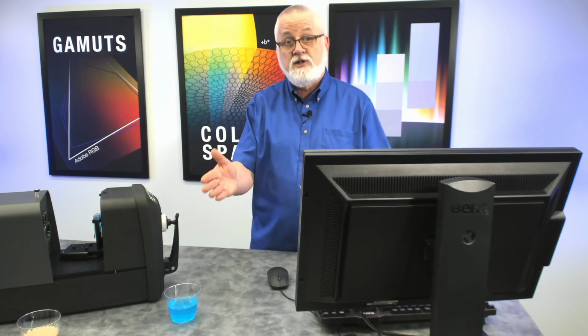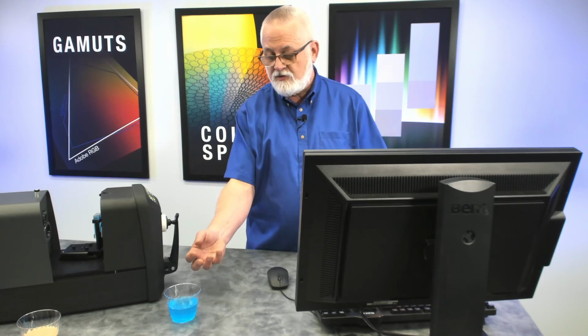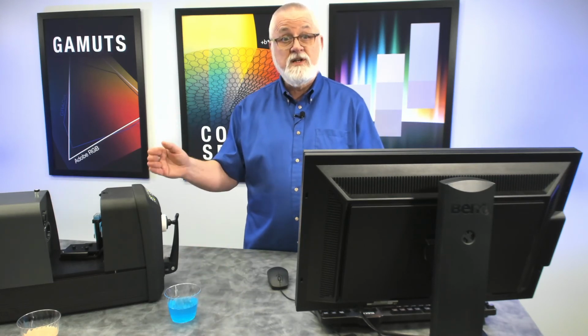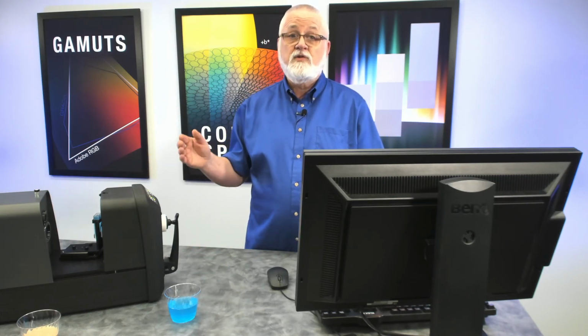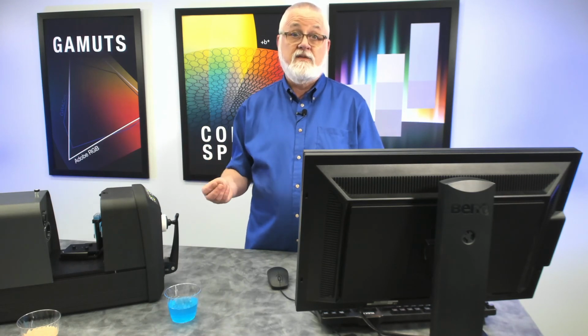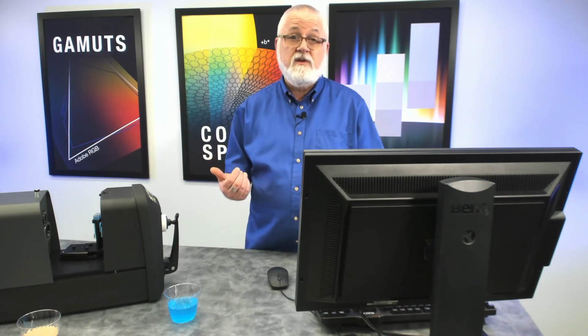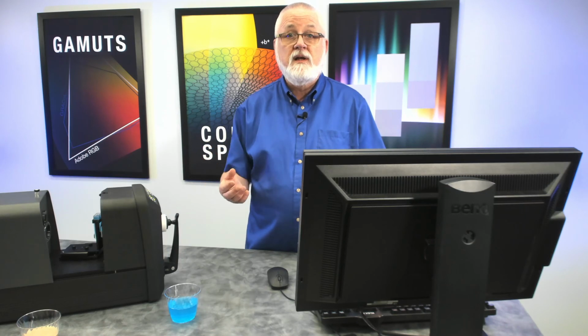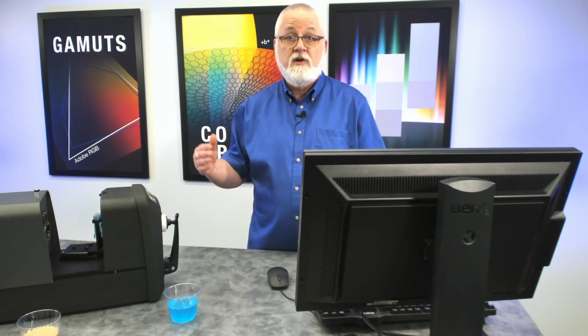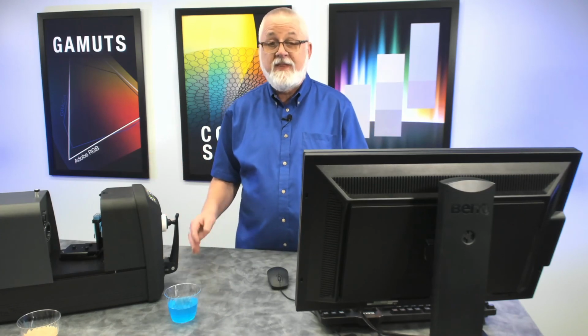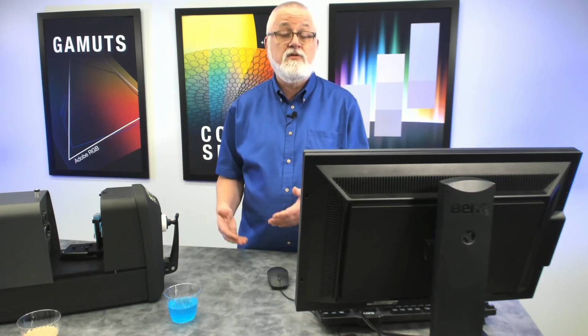It's just a way to measure liquid, and when the liquid is fairly transparent, sometimes a transmission measurement is better because transmission can tell us something about concentration. So if I'm adjusting how much color I'm putting in, more or less, to make it more or less transparent, a transmission measurement can help me do that. So that's how we measure liquids in a transmission mode.